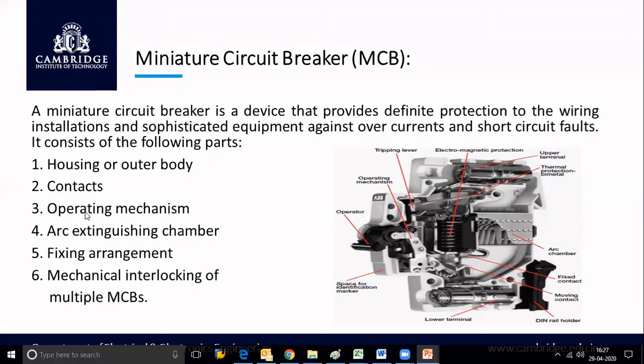Next, this is the operating mechanism, and the arc extinguishing chamber. You have the arc chamber here. When the two contacts are separated, an arc will be formed between them. That arc needs to be extinguished; only then will there be complete discontinuity of supply. For that, there is a chamber, known as the arc extinguishing chamber. Next, the fixing arrangement and mechanical interlocking of multiple MCBs. These are the main parts involved in the MCB.